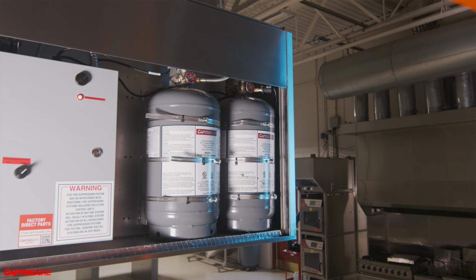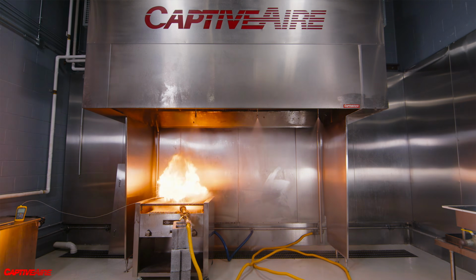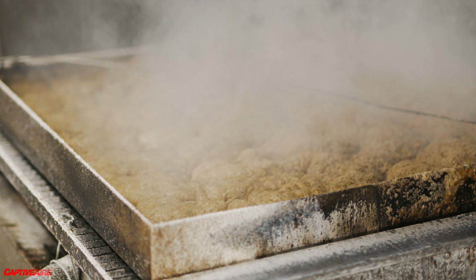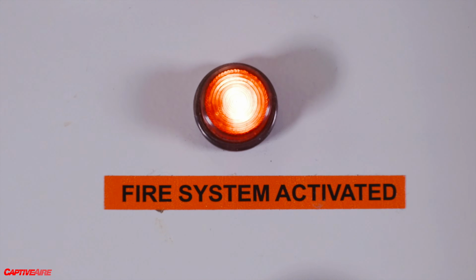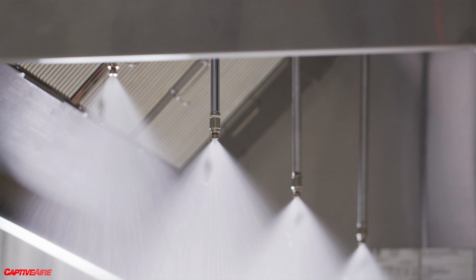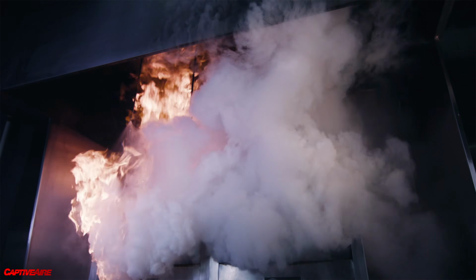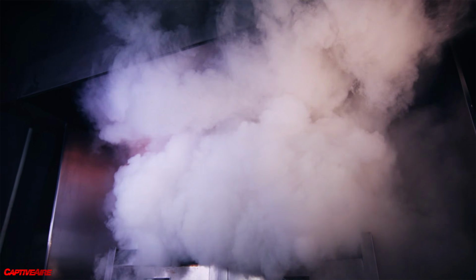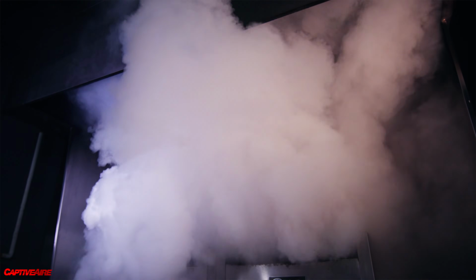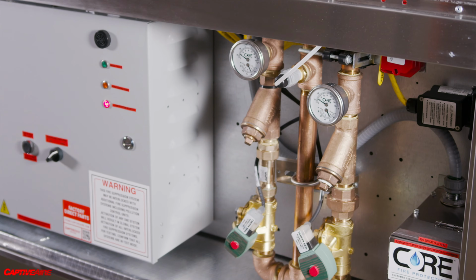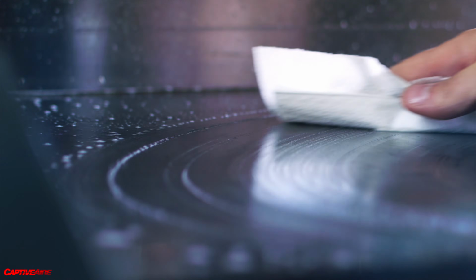In all of our testing, the tank system's performance is outstanding. That being said, in worst case scenarios, you could get reignition. If you get reignition, you've just used your tank to dump - you don't have any more wet chemical. That's where the core system comes into its own. The core system is going to continue to dump water while still monitoring temperature, and if there's a spike in temperature, it will continue to fire until that fire is 100% out. At the end of the day, go reset your MAD, reset the system, hose down some water and soap, and you're back up and running.